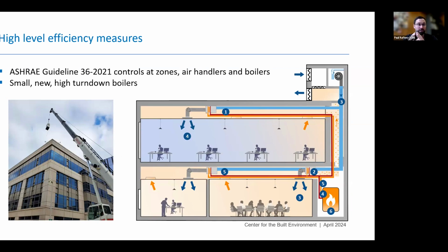At a very high level, we installed very aggressively sized, small, new high turn-down boilers that can operate all the way from 100% capacity down to 5%. The key element here is that we also did a full controls upgrade. Without replacing the actual physical controller hardware, we updated all of the control sequences and really tuned the building to operate well. This is much more in-depth than a typical retro-commissioning exercise.